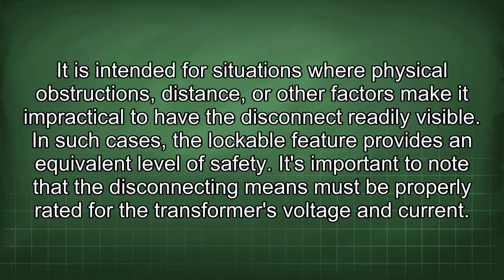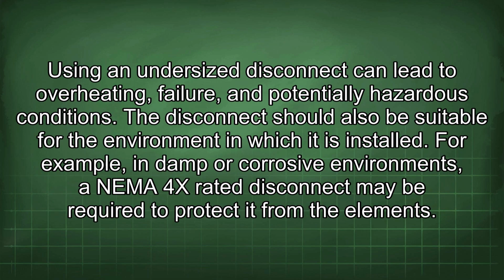It's important to note that the disconnecting means must be properly rated for the transformer's voltage and current. Using an undersized disconnect can lead to overheating, failure, and potentially hazardous conditions. The disconnect should also be suitable for the environment in which it is installed. For example, in damp or corrosive environments, a NEMA 4X-rated disconnect may be required to protect it from the elements.